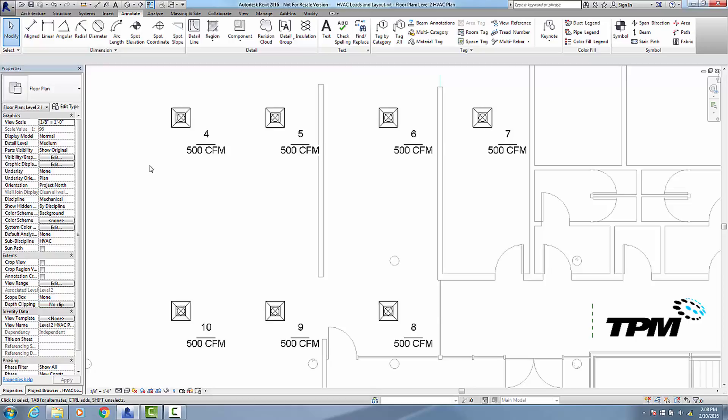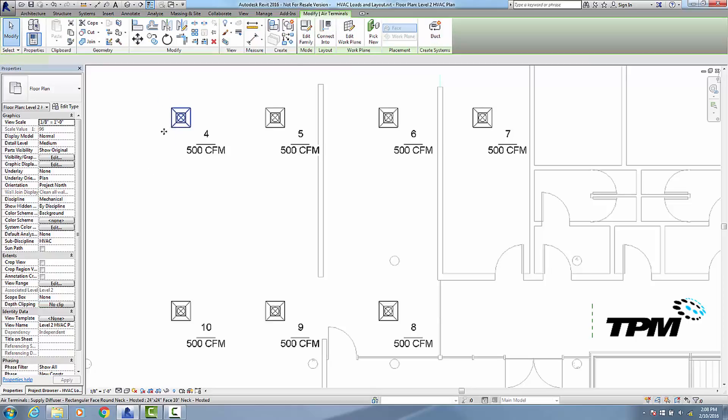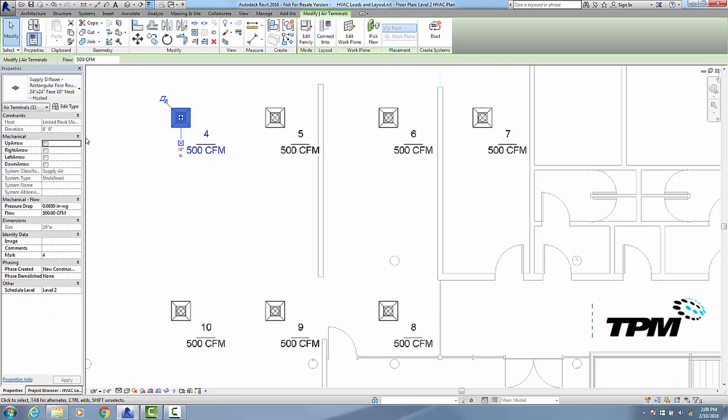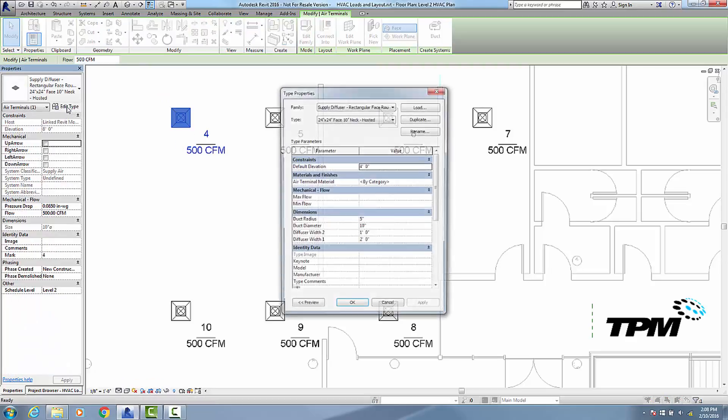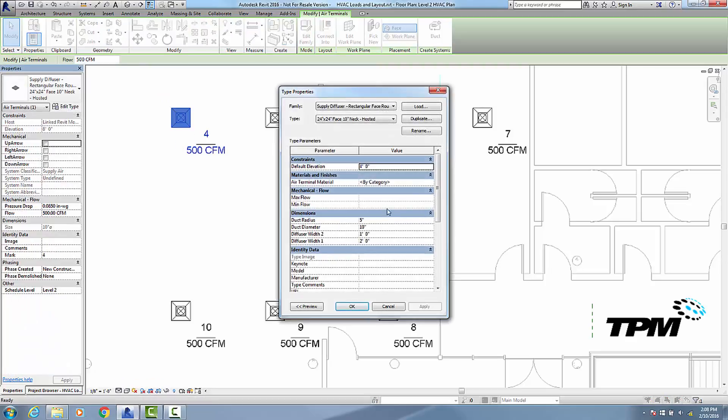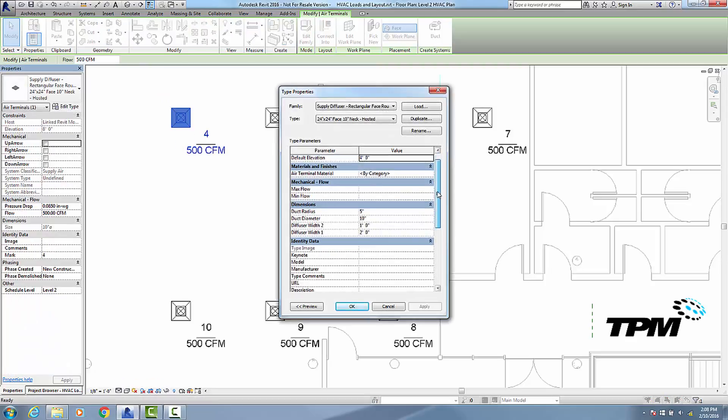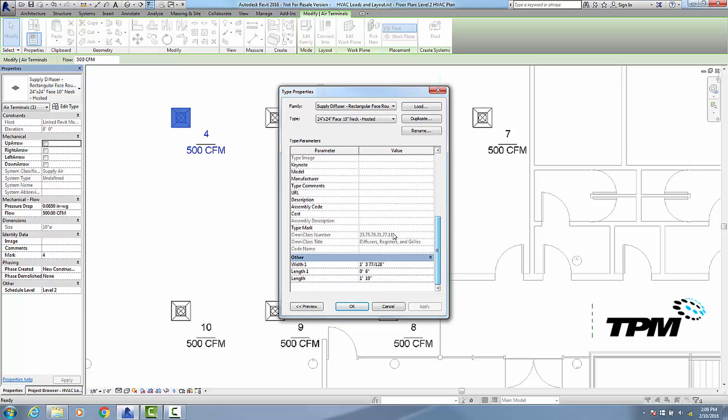So the first thing we're going to do in customizing this tag is change it so instead of the mark, it's going to use the type mark. Now before we do that, I'm going to click on the actual diffuser, go into edit type, and populate that type mark field with type A. So this is going to be our type A diffuser.